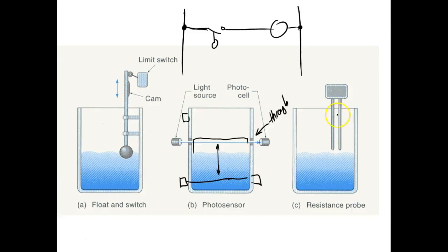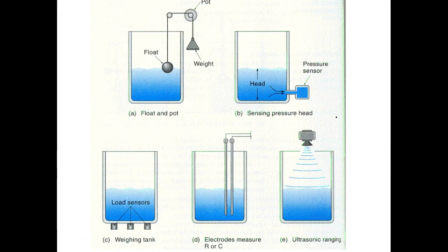This is a resistive probe. So what we're doing is we'll use a liquid that is resistive, but has conductive characteristics, right? You understand? And then what would happen is it comes up here and starts covering this up. Then we're changing the amount of resistance depending on the height. So this would give us a resistance that would be proportional to amplitude.